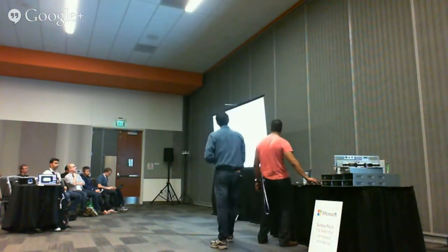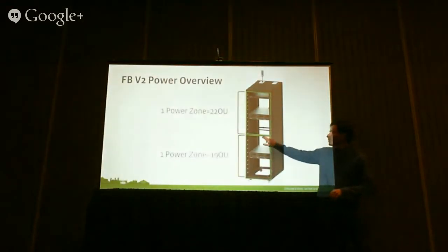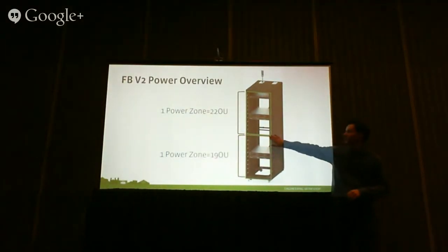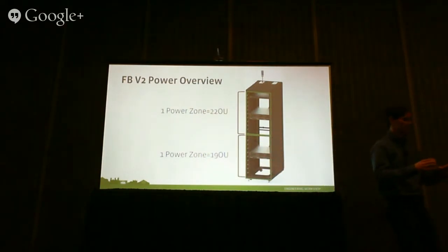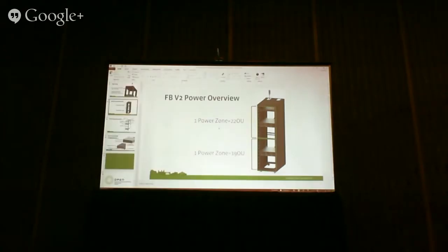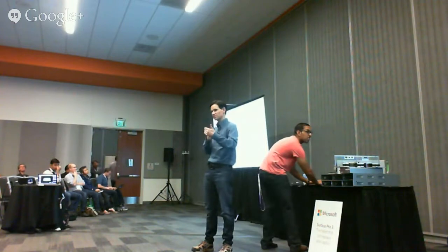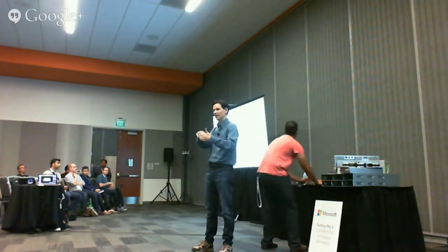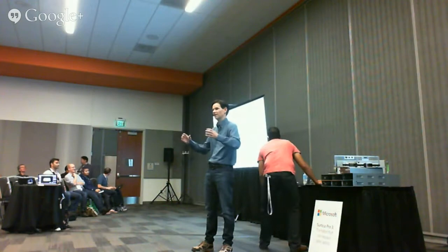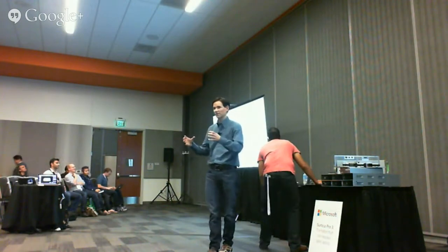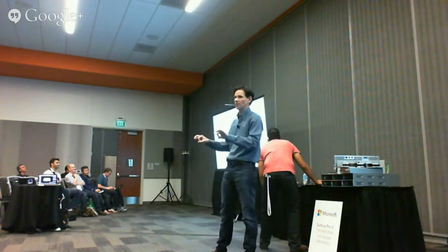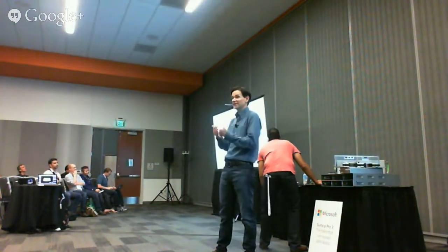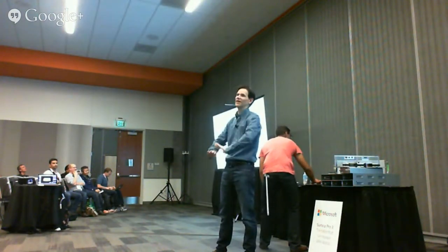You can imagine a little bit here, but the front one is behind these two green bars. So the bar actually sits in the middle of that column. The first half of the column is where the cables are sitting, and you've got the structural part where the IT gear integrates to the rack. That's where that front bar sits, in between the two IT components, basically the same plane where the IT gear would sit.